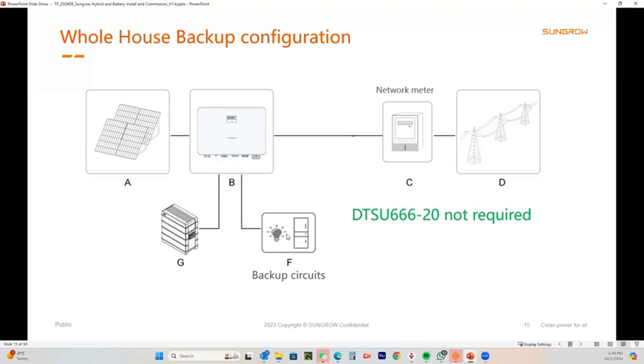Now what I'll mention about this is, yes, you can back up the entire house. When you're selling the system, you can sell it as whole house backup. Once you get the sale, of course, you can then discuss with the customer what they want to do. If they want the whole house backed up, that's perfectly okay. Or they could opt for just the emergency circuits like lighting, fridge, internet. Bearing in mind, the more loads they have on, if this goes into the backup mode and it's at night time, the longer the battery will last if they've got less loads. So if they're backing up the whole home, they might only get about an hour out of the battery, whereas if they only back up their emergency circuits, the battery could last them all night. So that's a discussion to have.